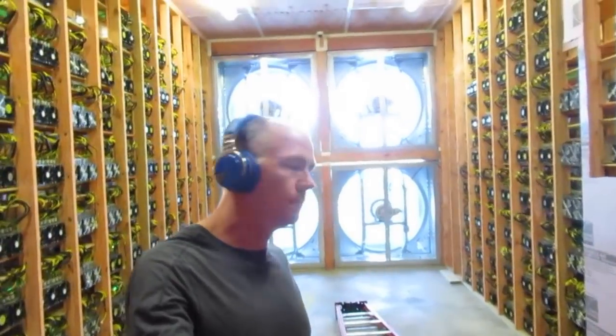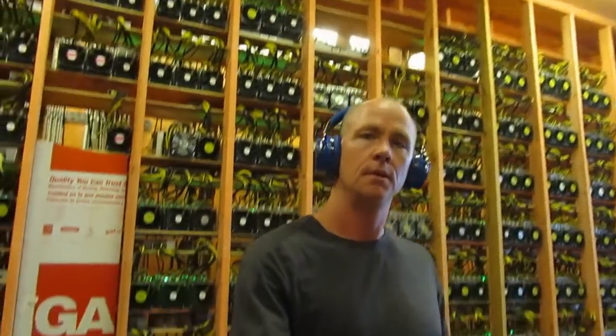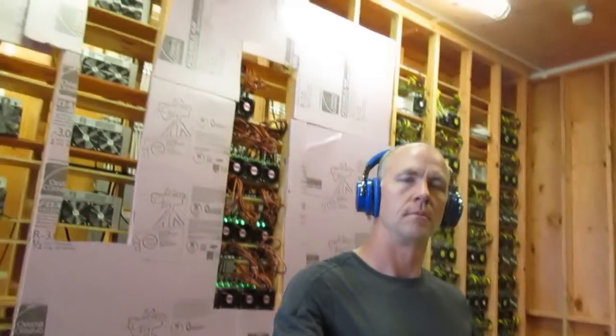So let's take you around for the full tour here, and we'll take you into the middle, which is the hot aisles. And even though the doors, it's fairly static pressure, it's still hard to open the doors. And here inside the hot aisle, we have 4 exhaust fans for a combination of 160,000 cubic feet per minute. So we have 8 fans altogether. You can see the exhaust of the miners are here. And you can also see where we've put in some HVAC sheeting to prevent hot air recirculation to the intake of the miners. These are expansion areas that we're going to continue to add miners to as we fill the space out. But you can see it's already pretty full.